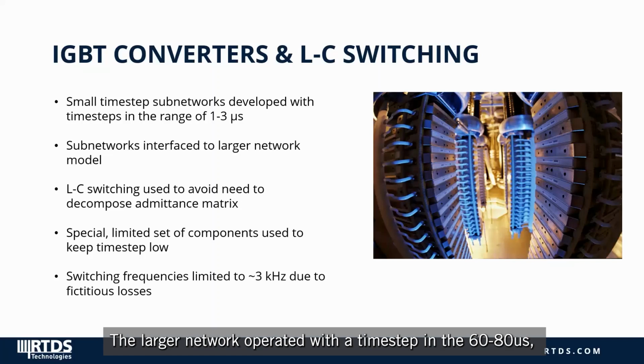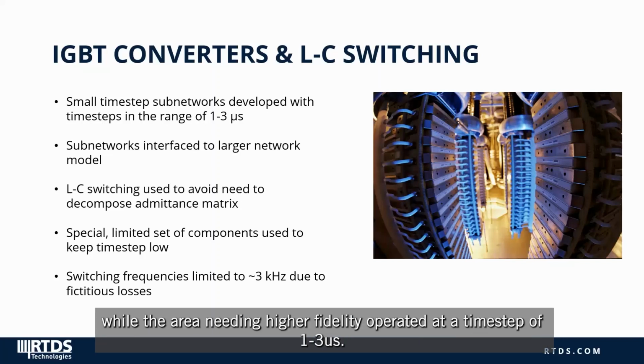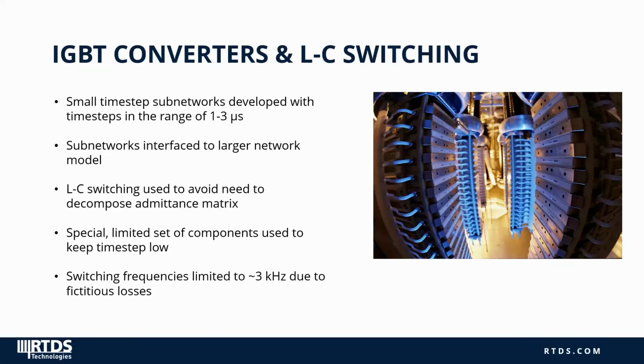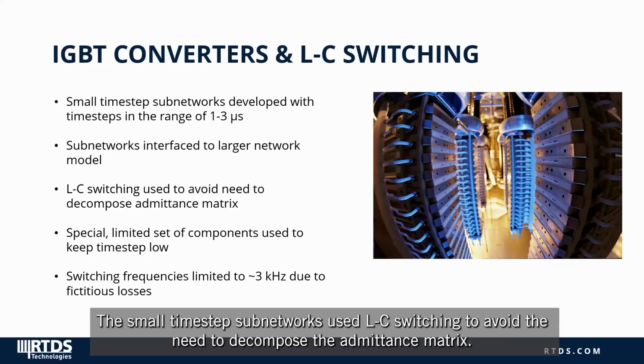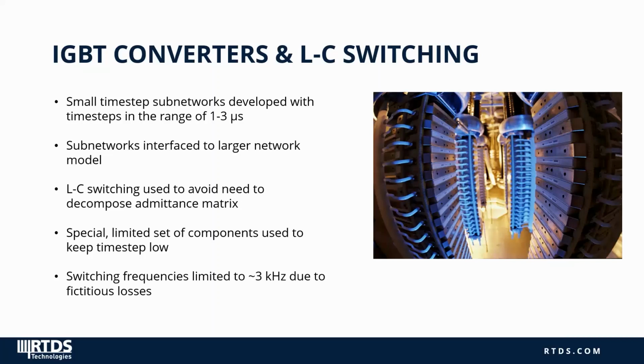The larger network operated with a time step of 60 to 80 microseconds, while the area needing higher fidelity operated at a time step of 1 to 3 microseconds. The small time step subnetworks used LC switching to avoid the need to decompose the admittance matrix.